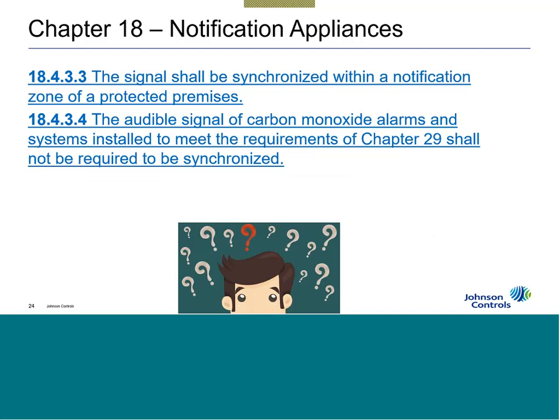So if you have a big floor, maybe it's being covered by 3 notification appliance circuits, I need to make sure that all 3 of those circuits, all of the horns, strobes, speakers, whatever they are, are synchronized. Meaning I'm hearing the tones, beep, beep, beep, I'm hearing the voice directions, they're all synchronized. Now, with Johnson Controls Autocall, that's not a big deal, right? If I have a fire alarm control unit and I use IDNet to 4009s, everything's synchronized whether you want it or not, in the whole building.